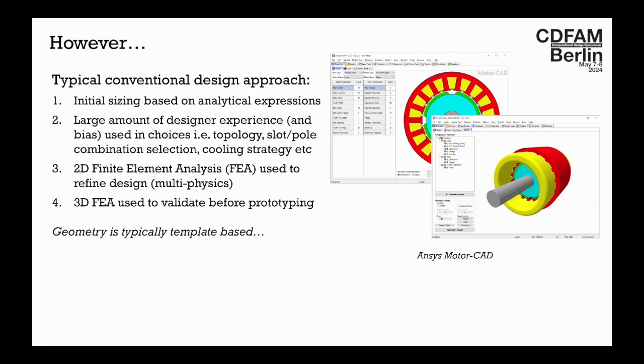So how do we design our design tools to get away from those biases, but also the complexity of solving an electromagnetic problem, which is really rather difficult because it's transient by nature? You have to couple your electromagnetic simulation to your thermal simulation and your mechanical simulation, so it becomes an inherently multiphysics problem. To get around that, in days gone by, because electrical machines typically have axial symmetry, we've essentially gone from analytical equations to 2-dimensional finite element analysis, and because that's very rapid on a modern computer, we can cope with that kind of design and simulation loop.